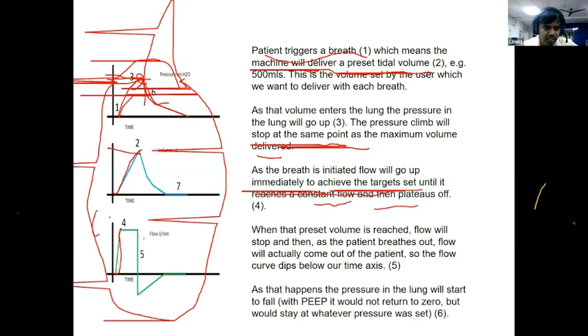And the flow, you see the flow curve. As the breath is initiated, the flow will go up immediately to achieve the target set volume, reaches a constant flow and then plateaus off. The flow goes smoothly up to 60 liters, which we set in the ventilator, then plateaus, and then it goes to the expiration phase. This is inspiration and then expiration. Then it goes to the zero level. So one cycle is over. So this is the pattern: this is the pressure curve, this is tidal volume, and this is the flow curve. Understood? So how is the physiology happening?